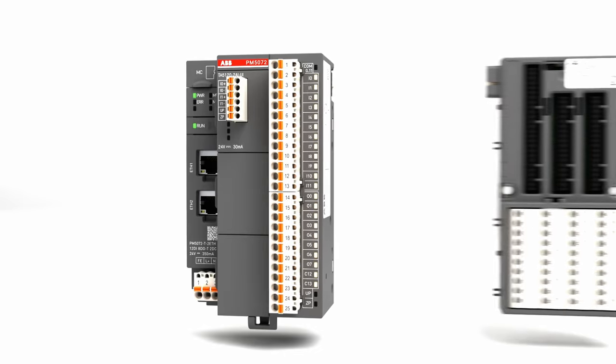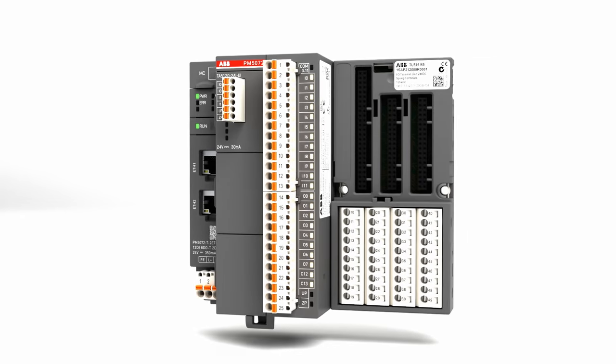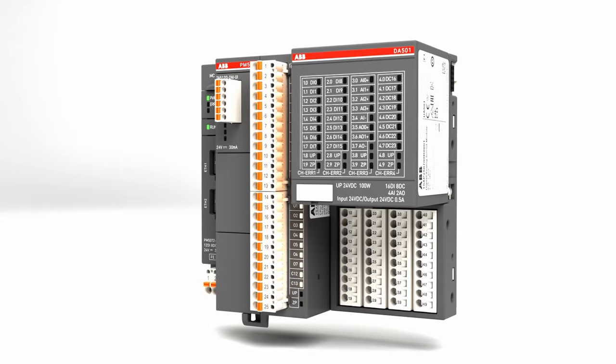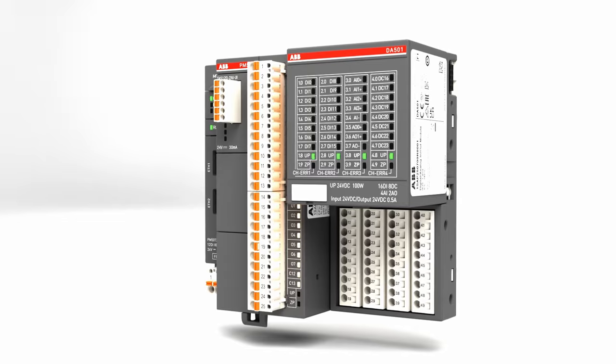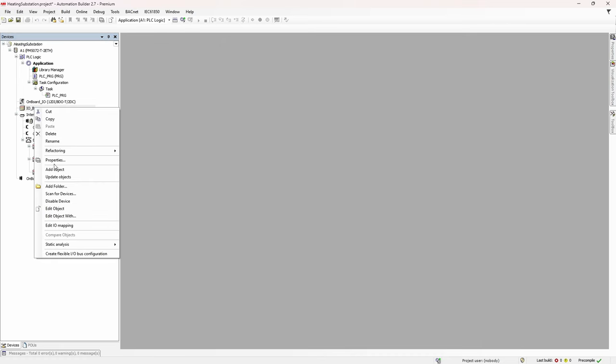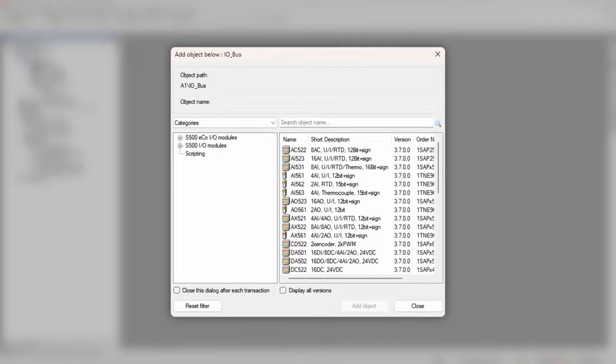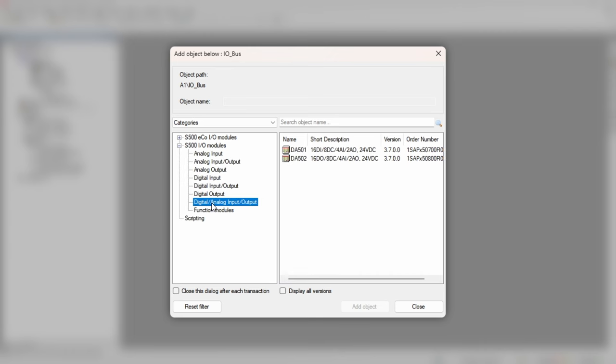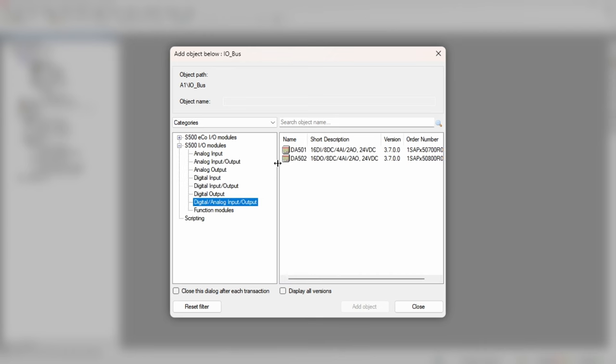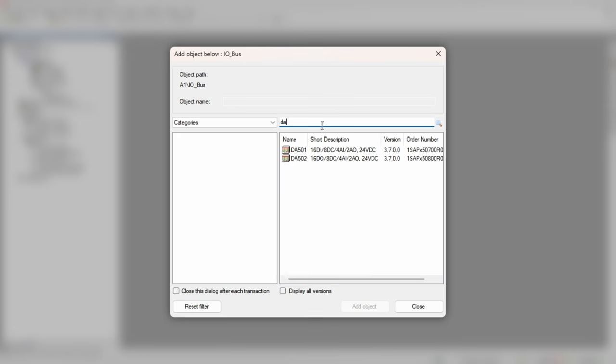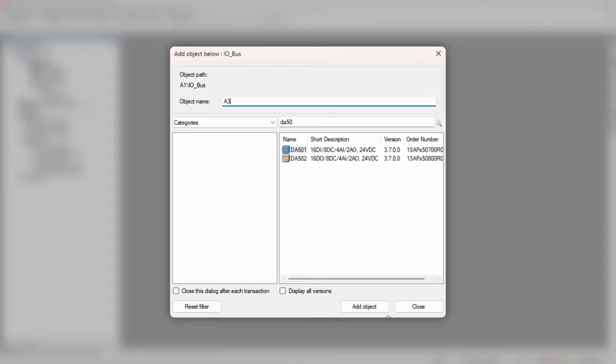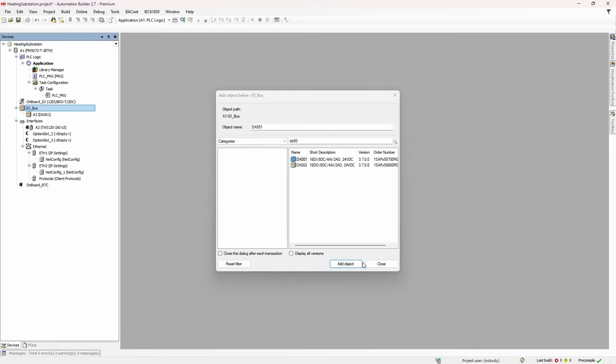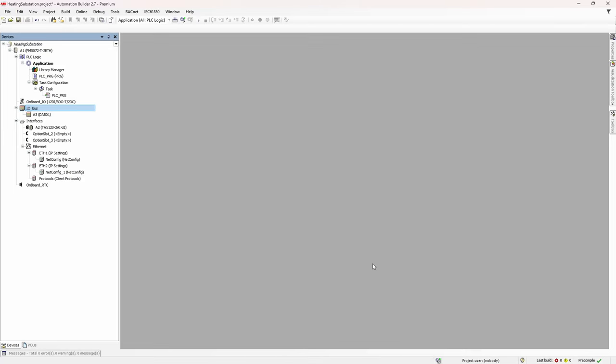Now we need to add DA501 module to the CPU's iobus. Right click on iobus element. And again, if you know which category the module is in, we can navigate there, or we can simply type the name to the search box and select from the filtered out list. Don't forget to give the module a proper name. But even if you forgot to do so, you can rename the module later.